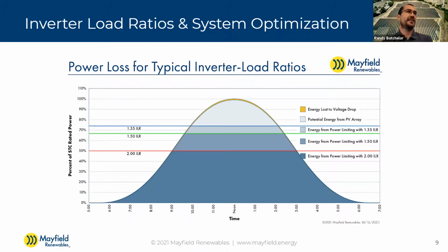This is a clarifying question: is loading ratio different than DC to AC ratio? Just for people who may not know if those terms are different. No—loading ratio is DC to AC ratio. It's just the rated DC power at STC to the rated AC power output of the inverter.